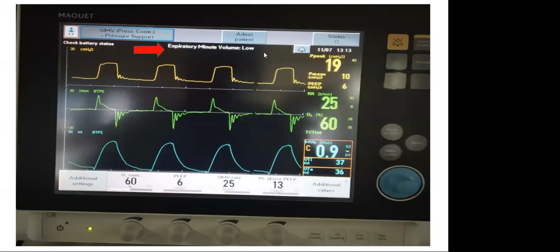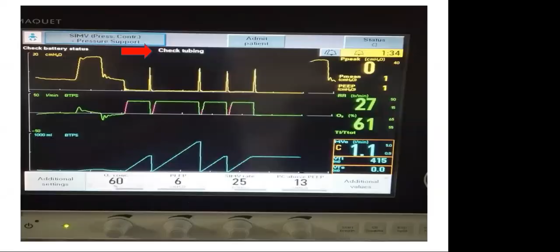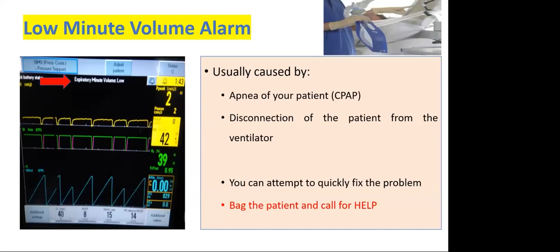So what is it here? You can see the minute volume is low, and there is a full leak. It's a low minute volume alarm. Usually it is caused by disconnection of the patient from the ventilator, or leaks in the circuit. So what you have to do is connect to the test lung and see if the leak still persists. If it still leaks, there is a problem somewhere in the ventilator circuit. Meanwhile you have to bag the child, and especially if the child is on a cuffed tube, see how the cuff is, check the cuff pressure and reinflate if needed.